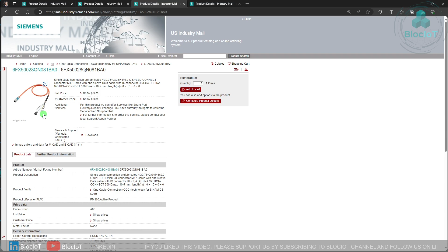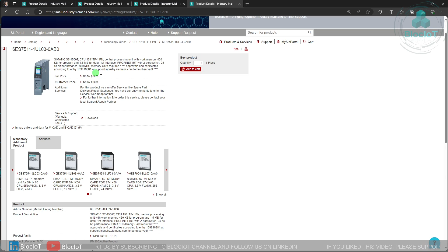Last but not least, we use an S7-1500 series PLC to control the drive. One thing to keep in mind: you have to go with a T, or technology, CPU if you are controlling a servo motor. That's why in this example I'm using a Siemens S7-1500 TF.